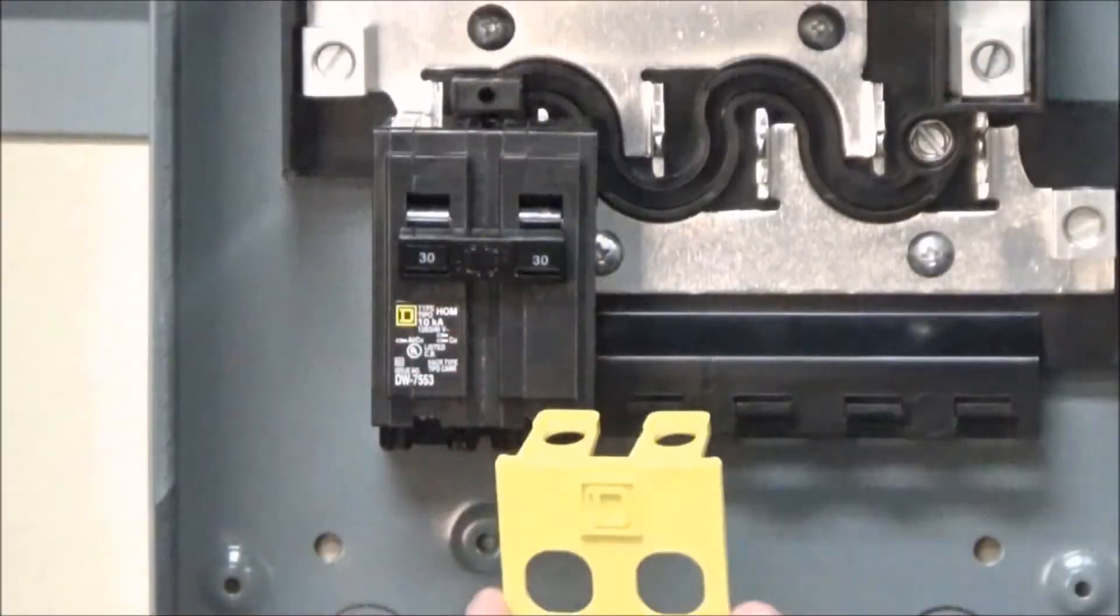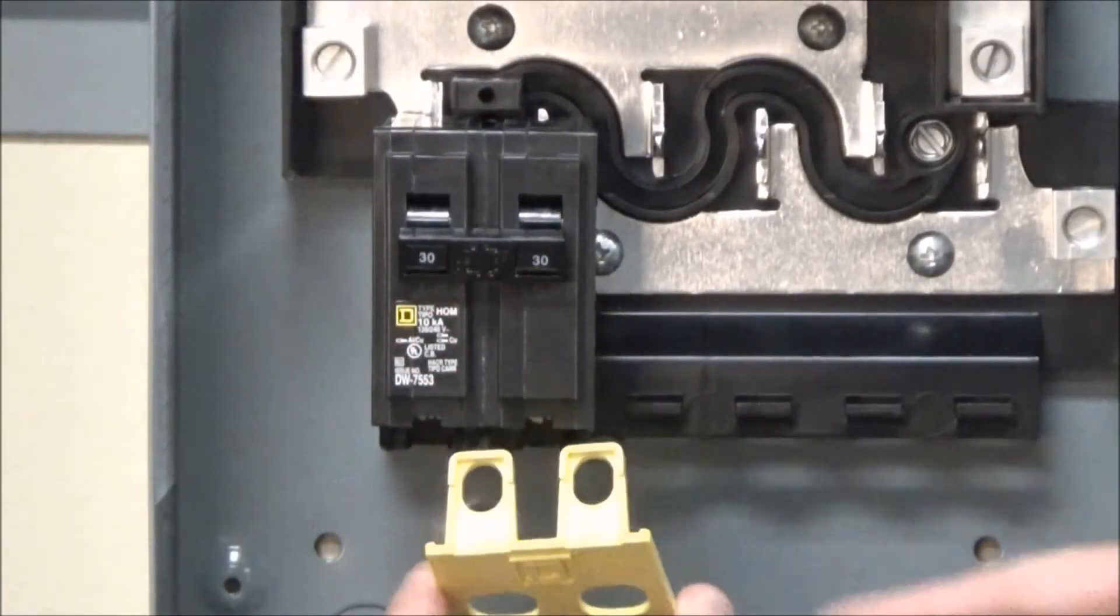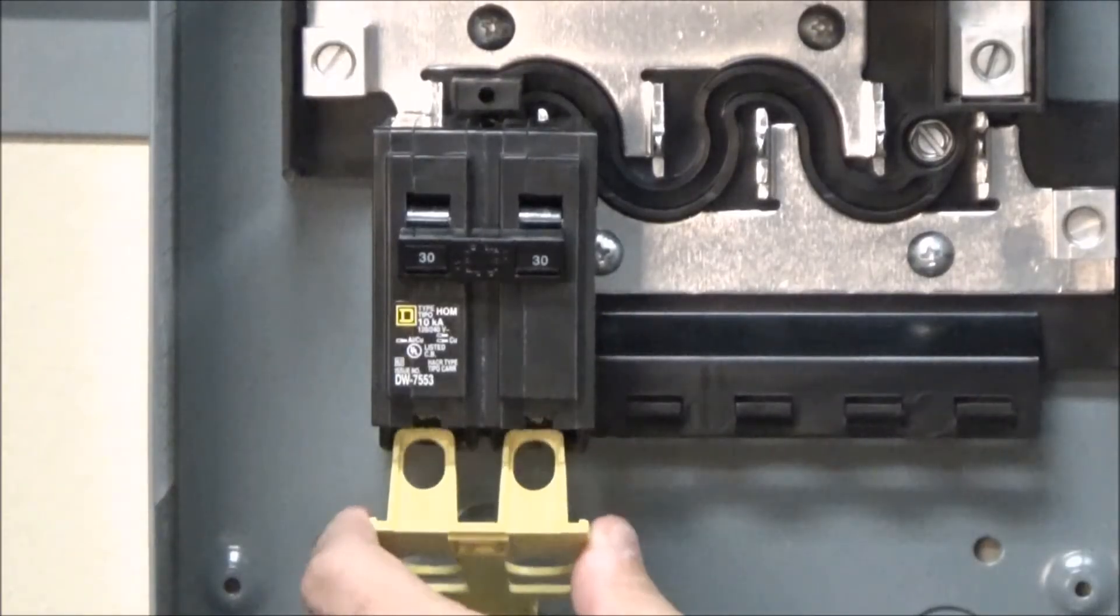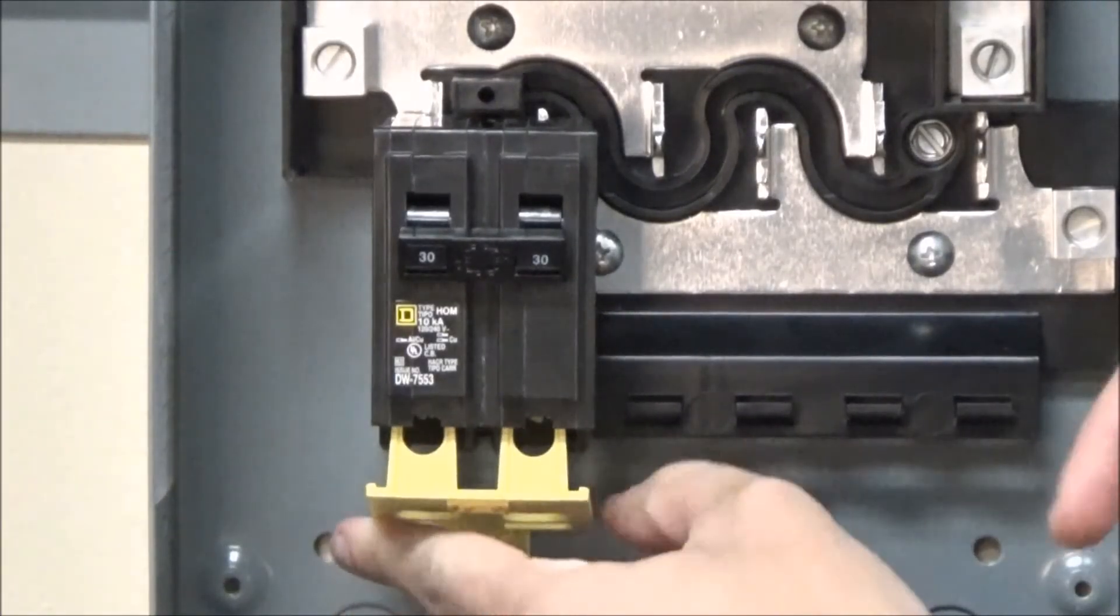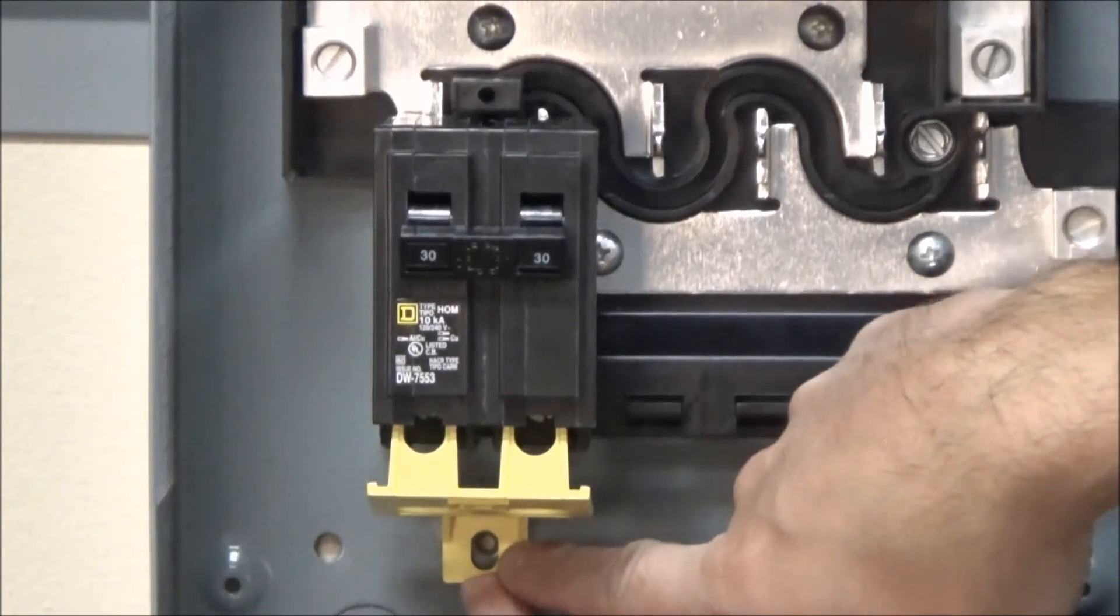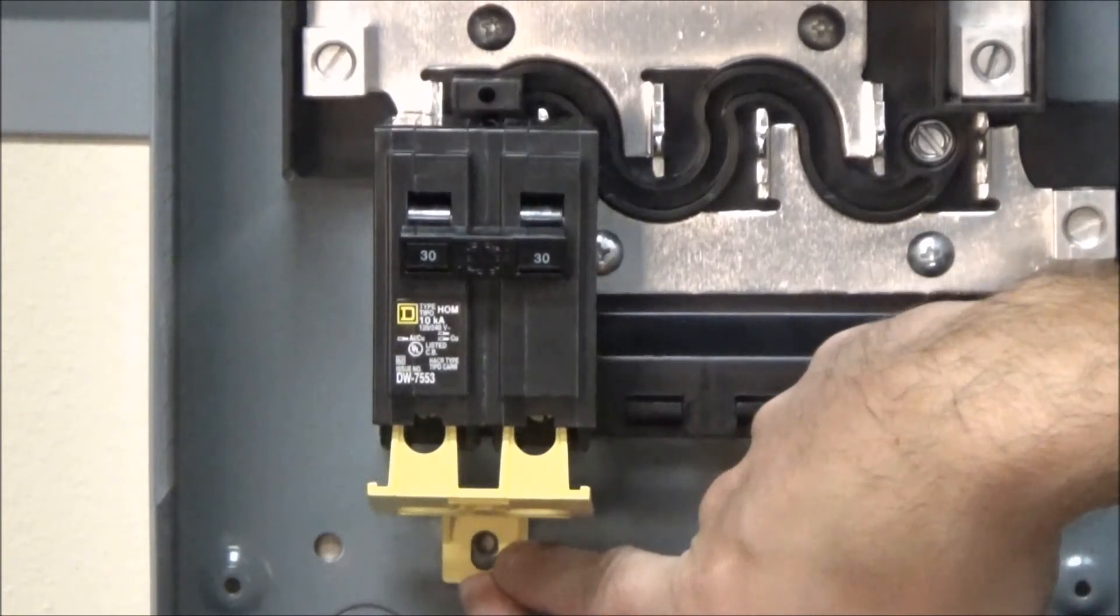To install the service entrance barrier, you will insert the tabs on the barrier into the circuit breaker slots, and then you will take the mounting screw and insert it into the extruded hole located on the enclosure, which is only on the new 2017 HomeLine panels.